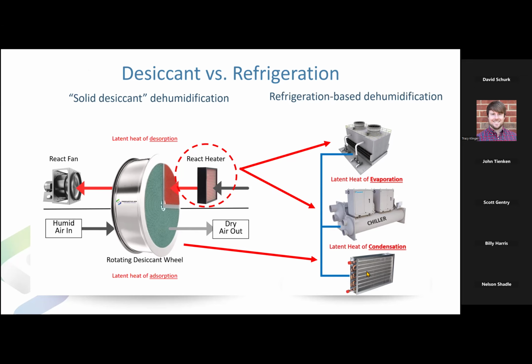Just like its counterpart, let's take a chilled water system, for example, requires electricity to run a compressor, to run pumps, to run a cooling tower and fans, and create lift between indoors and outdoors to get rid of what I have absorbed in the cooling coil and discharged through the cooling tower. So this is not inefficient. It's not weird. It's not an unsustainable way to drive this system. In fact, it's very efficient, very sustainable, and it parallels exactly what we have to do in more traditional systems. So now that you've understood how it works, you see heat down here in the process airstream. It's not weird. It's just a part of psychrometrics. It's in this other system as well. We just don't see it. And you see heat up here, which isn't how we do it in a traditional system.